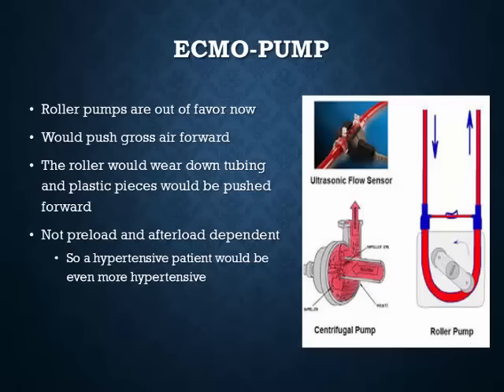There were two types of pumps. Back in the day, roller pumps were commonly used but are now out of favor. With roller pumps, all the tubing contents — including air and pieces of plastic — would be propelled forward into the patient. Many people comment that this may be why earlier ECMO studies weren't as successful, though it was difficult to measure. Centrifugal pumps have now replaced them.